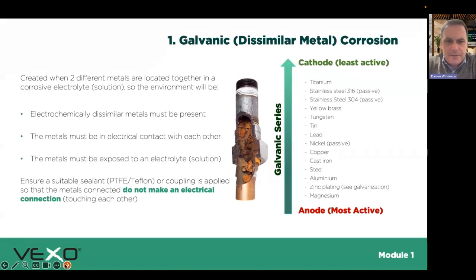So galvanic corrosion, in the case of corrosion, different types of corrosion. Galvanic corrosion is very much when you have dissimilar metals, and the further apart that they are on the galvanic series, you can expect to see a higher rate of chemical reaction taking place at that location where the two metals meet. But for it to happen, you need to have water or an electrolyte passing through. So you won't have the same issue if you imagine a flange connection on a pipe where the bolts are on the outside, there's no water passing over. It's not such an issue. But certainly on the inside, where we're passing that water through, two different metals meet. So we need to make sure they're not in electrical contact with each other. So it's very much understanding the right types of joints to use, and certainly plenty of PTFE or Teflon tape.